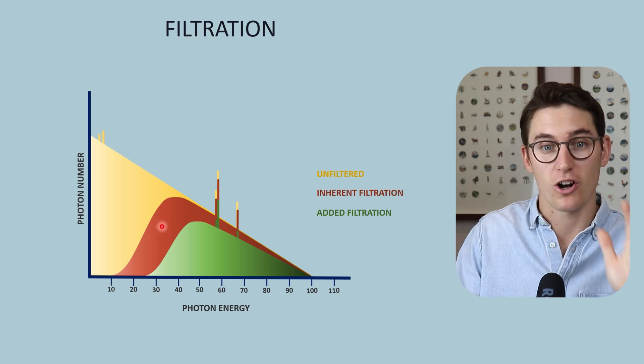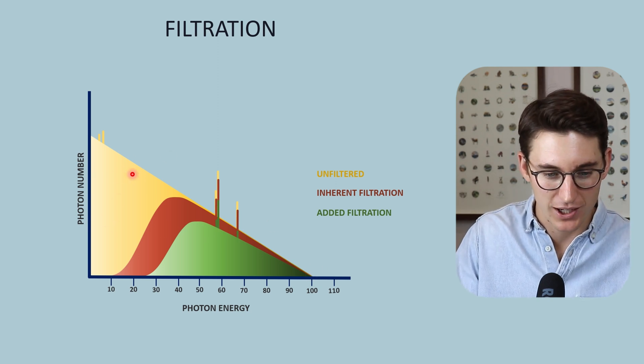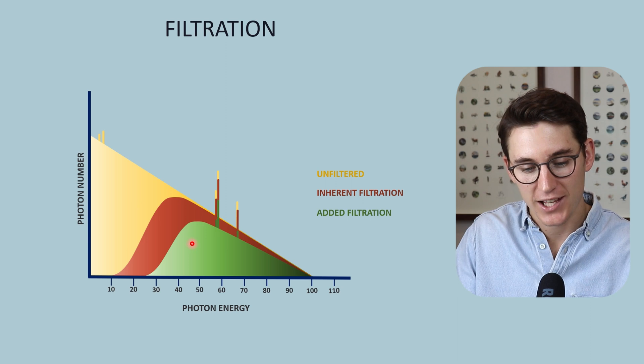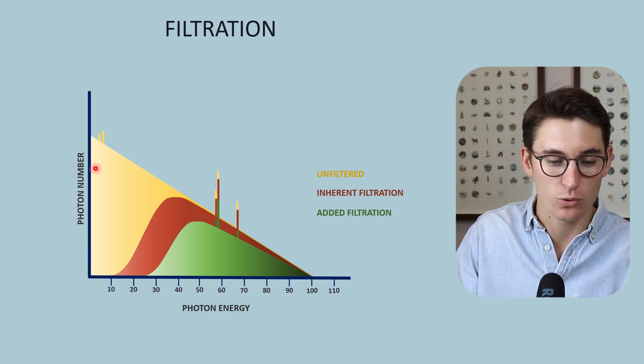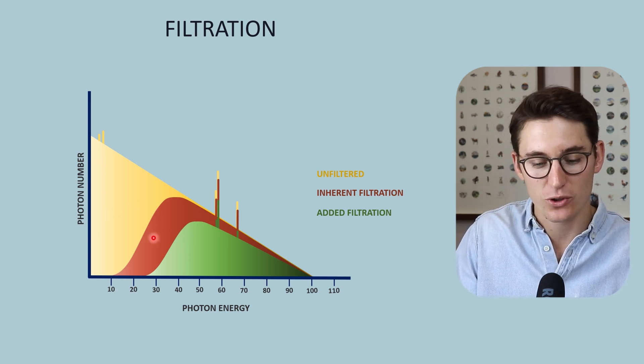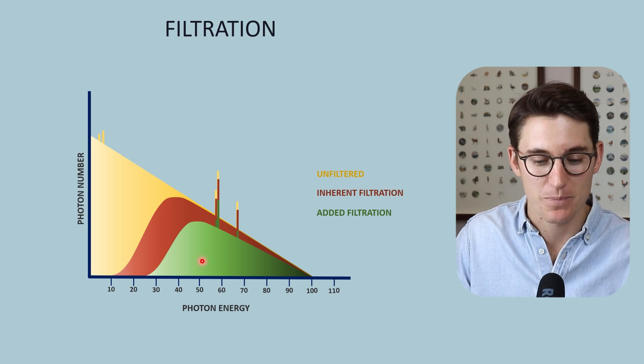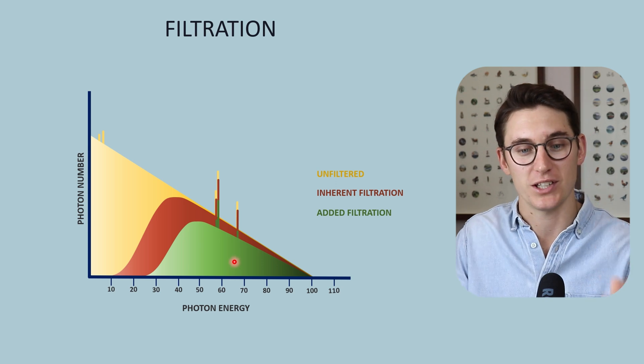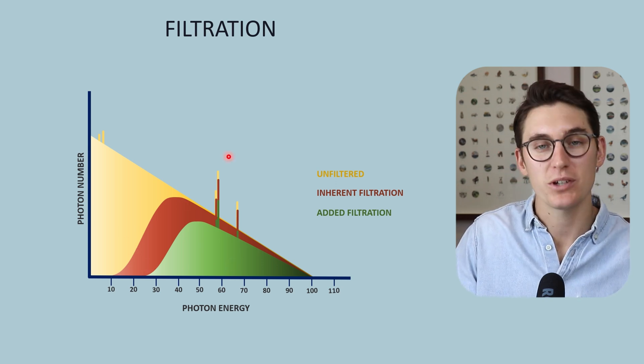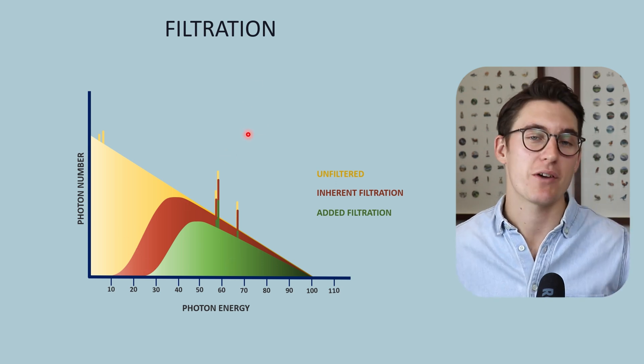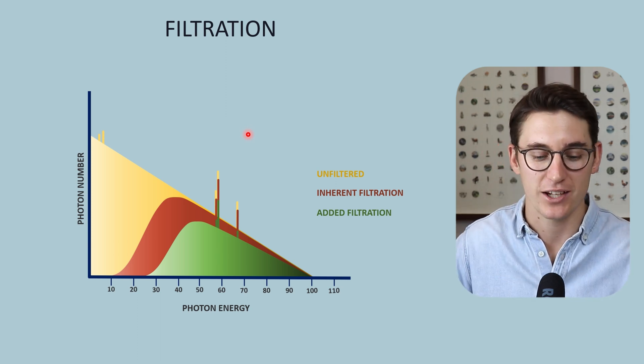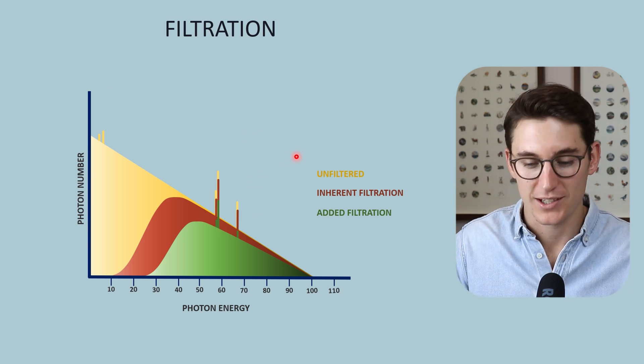Looking at the graph, an unfiltered spectrum, an inherent filtered spectrum, and an added filtered spectrum all result in sequentially fewer photons — we have decreased our x-ray beam quantity. Simultaneously, we have increased the average energy of each spectrum. As we filter our x-ray beam, we preferentially remove lower energy x-rays and increase the average energy of our x-ray spectrum.